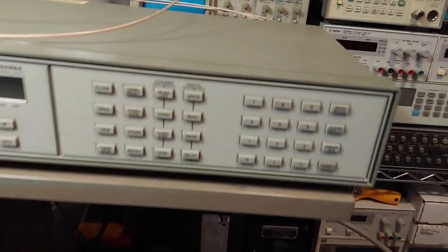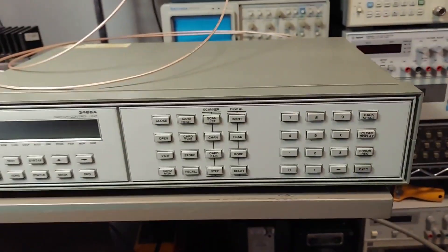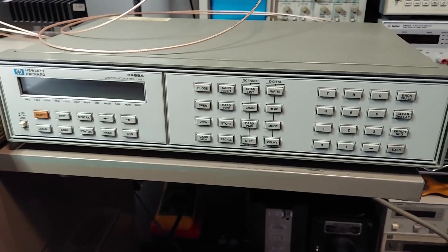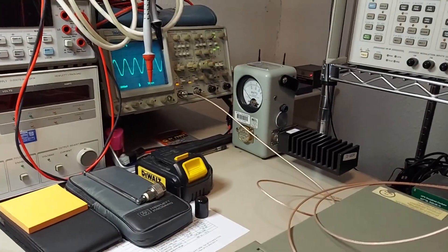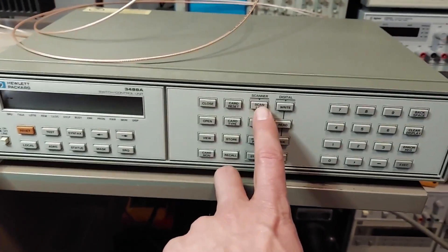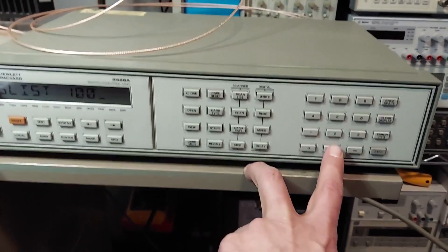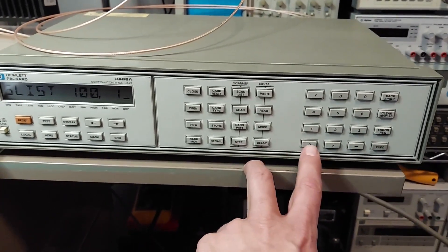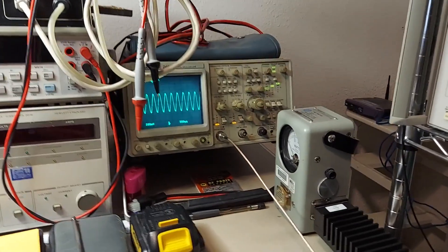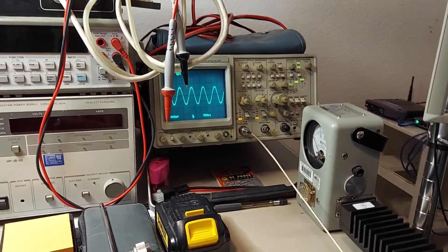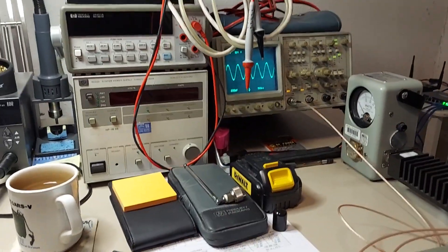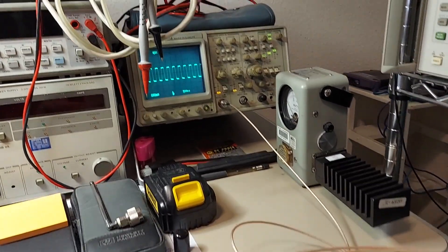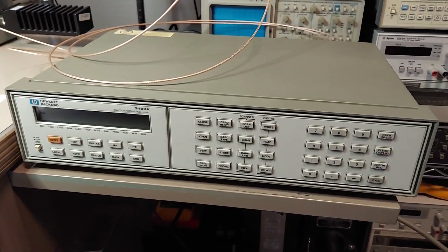And you don't have to open the previous relay, it automatically does it for you. You can't close both relays at once on the same port, at least with these cards anyway. Now if I want to just toggle between those two and see what's going on, we can set up a scan list. So let's do it again, set up a scan list. We're going to set up card one port zero and card one port one. Now use the step button and step back and forth between those two, allows us to compare the signals. So we could actually go to square wave on that one. Cool, really neat.